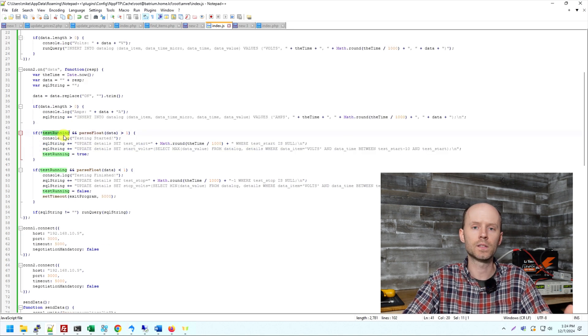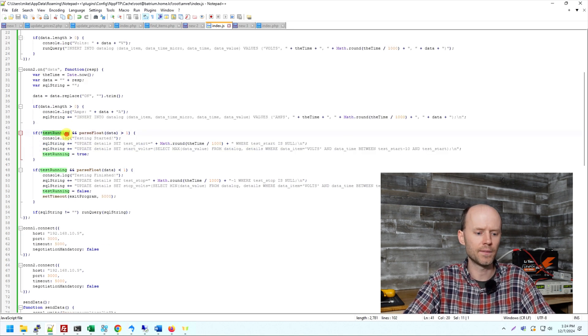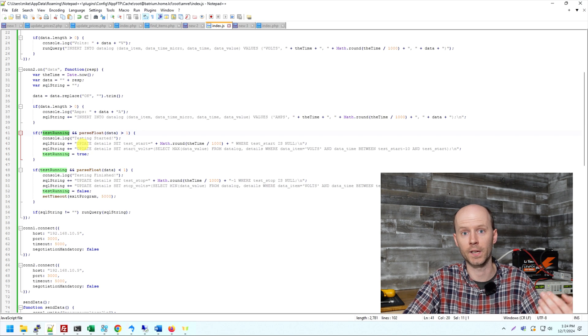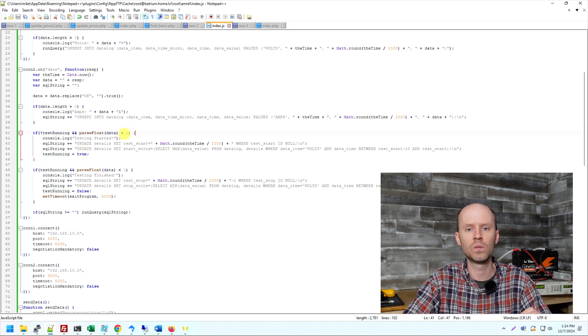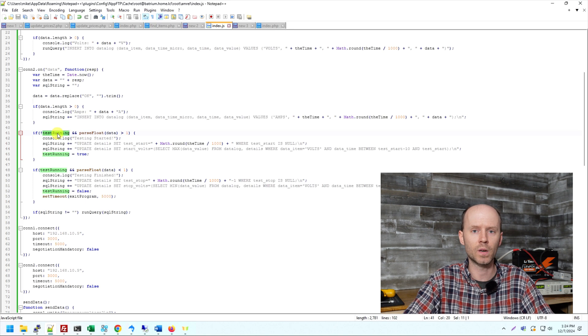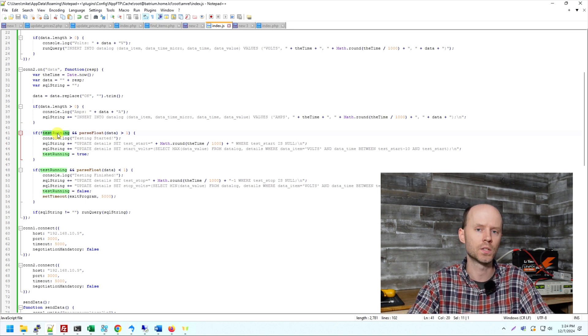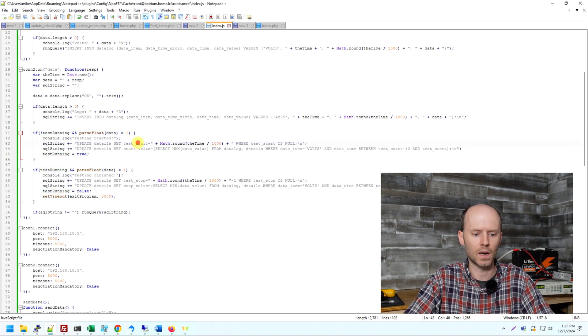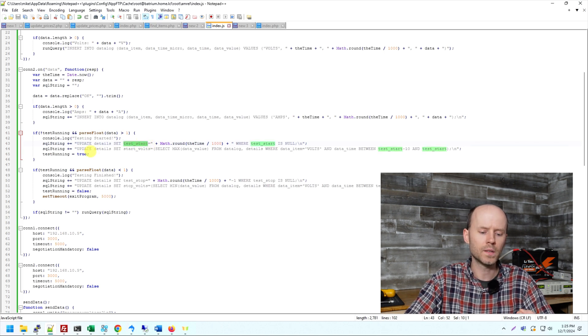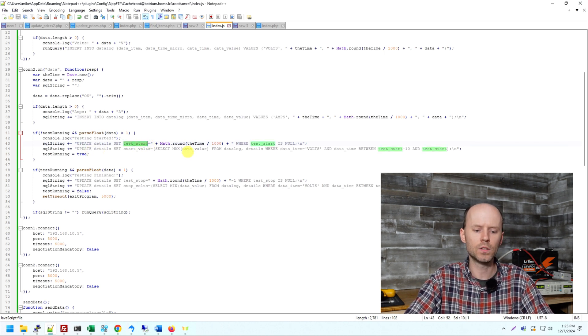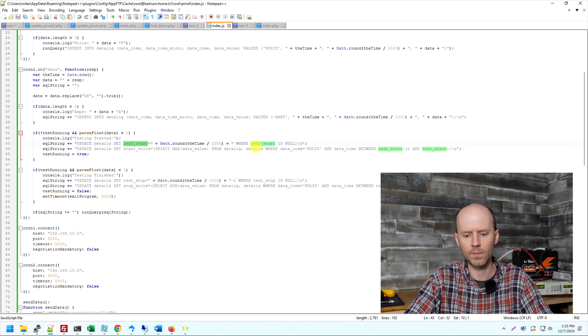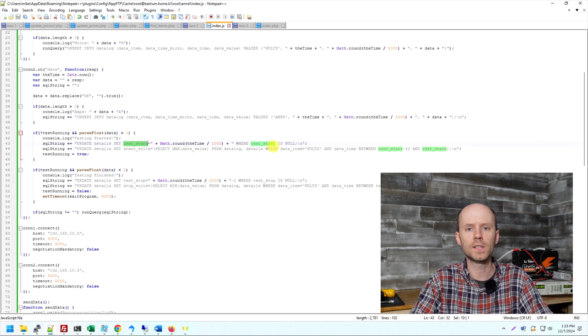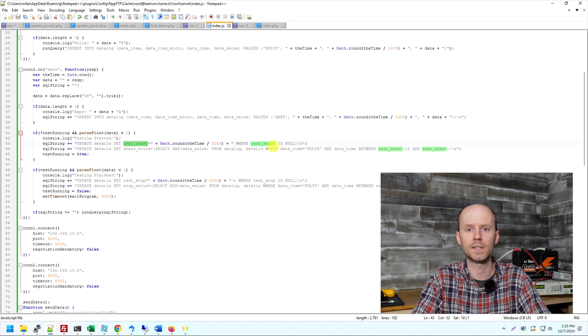Now to gather the start and stop time and voltage, I have a Boolean variable called test running. By default, test running is false. So the first time we see a current come back that is greater than one amp and the test is not running, we'll know that means that the test has started. So as soon as we notice the test has started, we're going to capture the test start time in seconds. We're also going to capture the start voltage. And to do that, I am selecting the maximum voltage from the data log table, current time up to 10 seconds prior. So there's a 10 second buffer in there to grab the voltage before the test actually started.